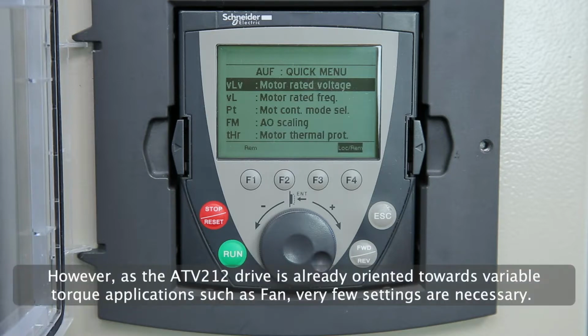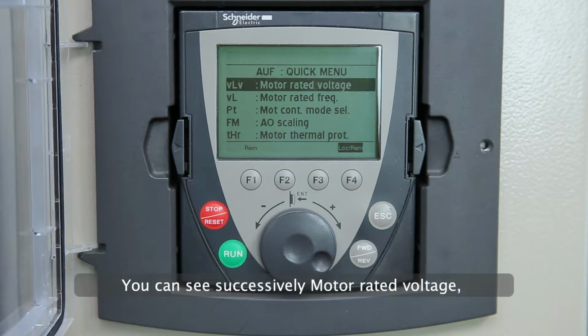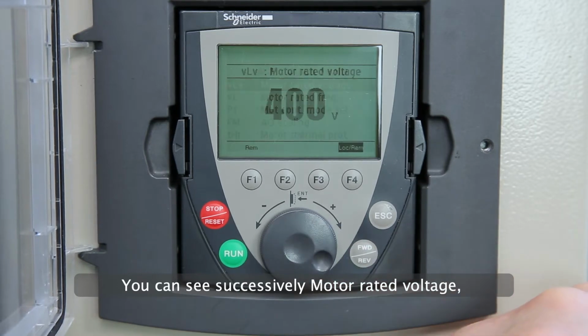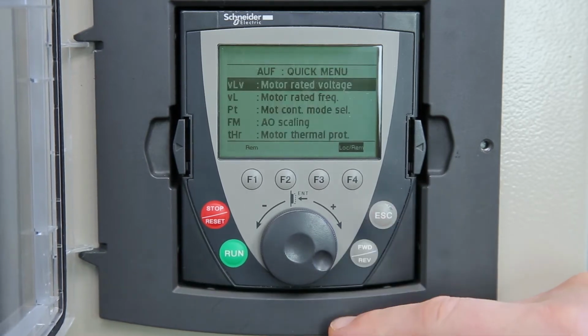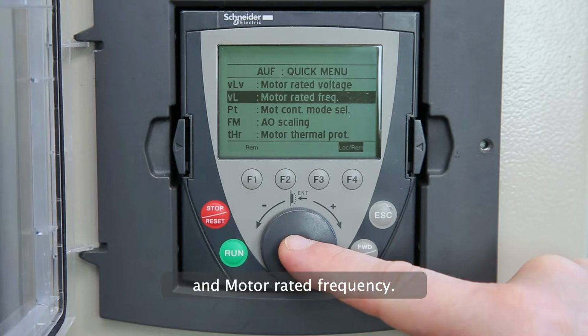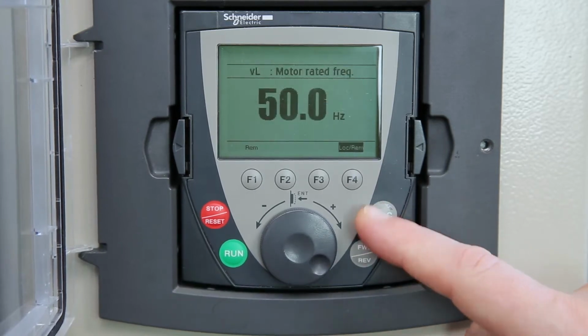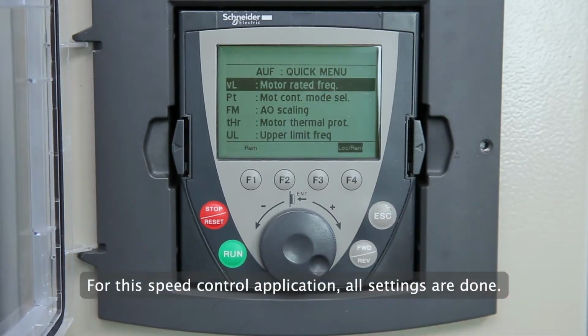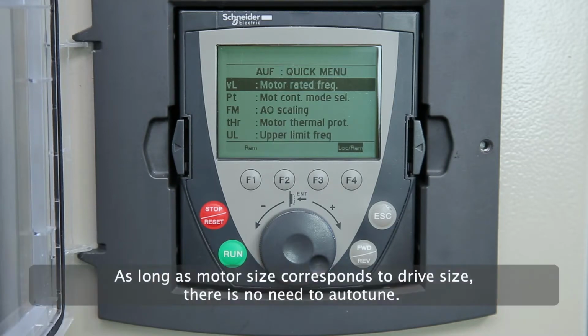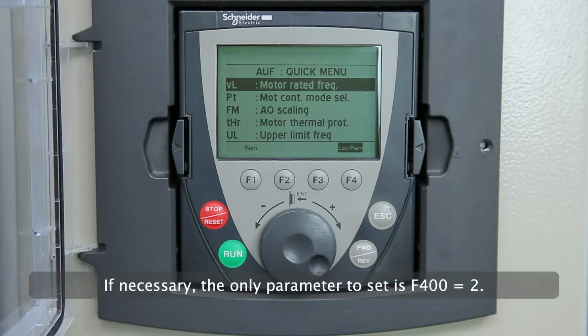However, as the ATV212 drive is already oriented towards variable torque applications such as fan, very few settings are necessary. You can see successively motor rated voltage and motor rated frequency. For this speed control application, all settings are done. As long as motor size corresponds to drive size, there is no need to auto-tune. If necessary, the only parameter to set is F400 equals 2.